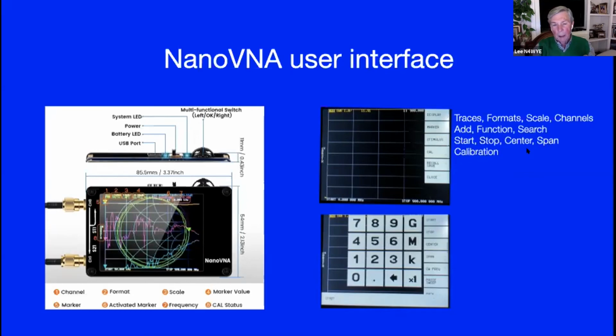And then the bottom one here is calibration. Some of you may have heard a lot about calibration, but it's basically making up for the shortcomings the device has. So if you want to look at 40 meters with a lot of data points, you have to calibrate for that frequency range. If you want to look at a broad antenna to see what the multiple resonant points are, just as a first order approximation, then you need to calibrate it for that frequency range. It's not that difficult. It's fairly straightforward.